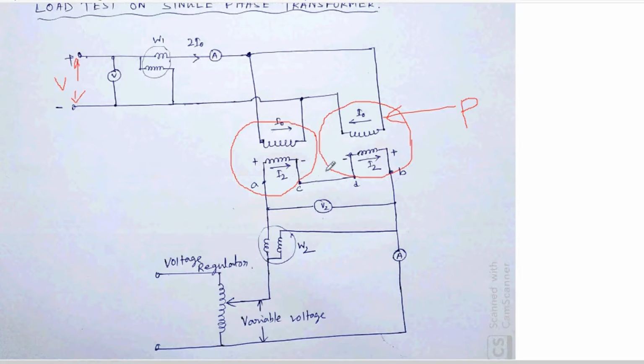Whereas the secondaries are connected in series and also in phase opposition. Phase opposition means when the polarity here is positive, here the polarity is negative. So that means this voltmeter will read zero. If the induced EMF in one secondary is E and in the other is also E, the voltmeter will show E minus E, that is zero. If the voltmeter shows an additive reading, that means these two are not in phase opposition. So you have to keep these two windings in series and phase opposition.